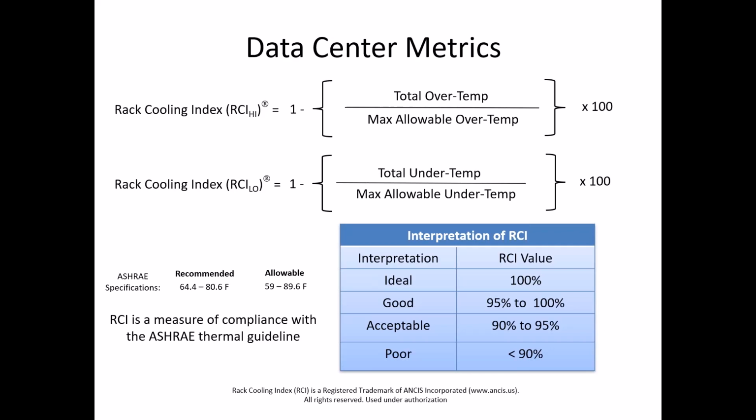And that is very, very important, because imagine that you had a situation where a few points were right at the maximum recommended, and another case where they are like 10 degrees higher than the maximum recommended. That's different, right? There's still just a few points above the recommended, but the difference is that in the second case, they are much above the recommended range. So that's going to give another RCI value.